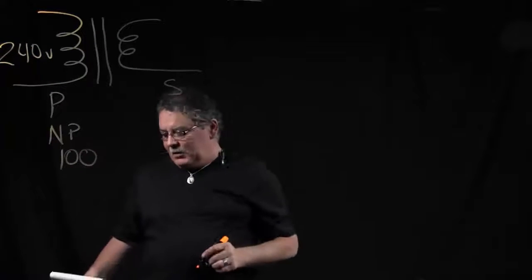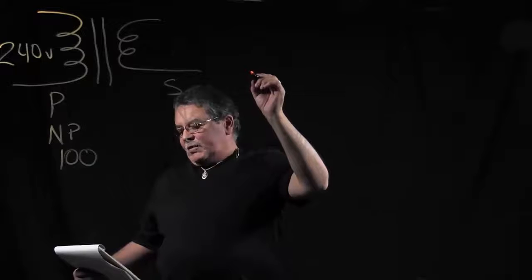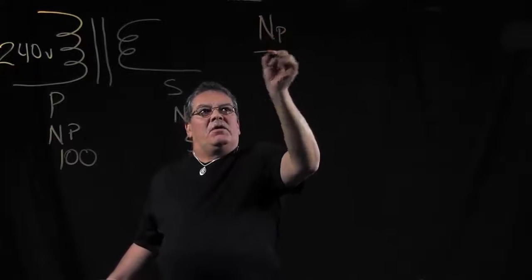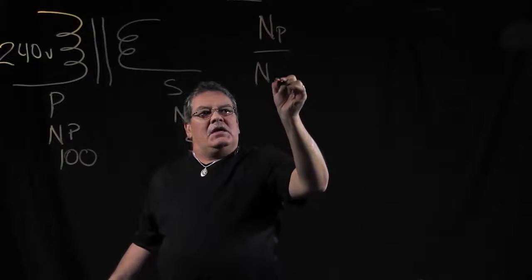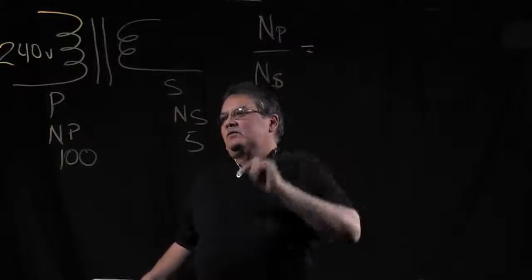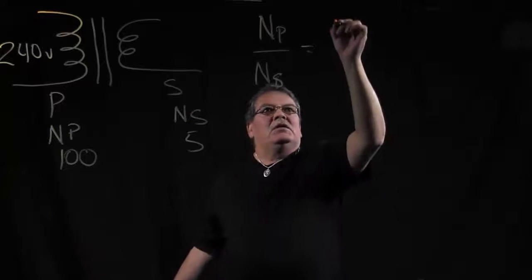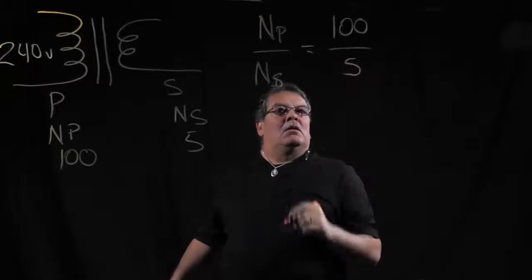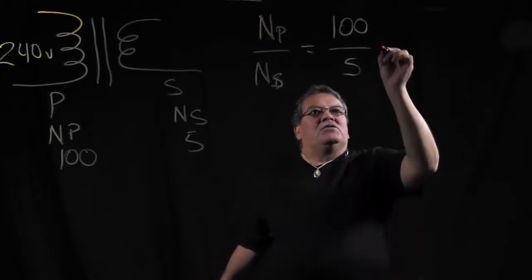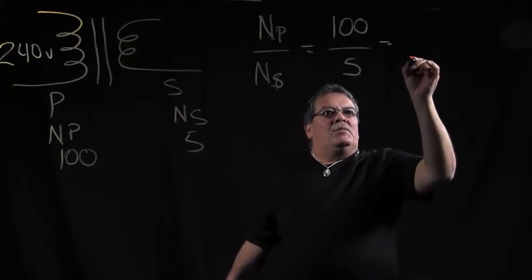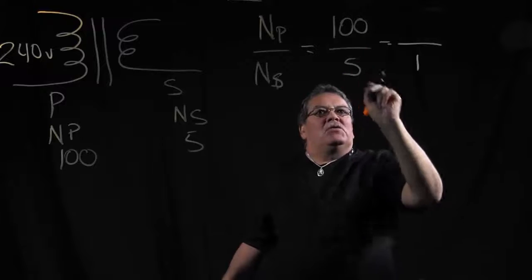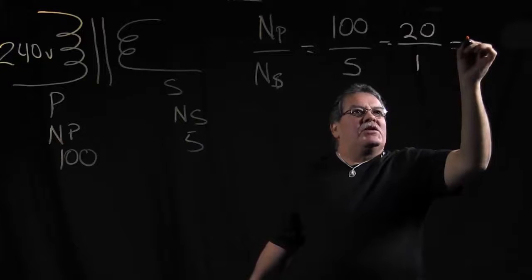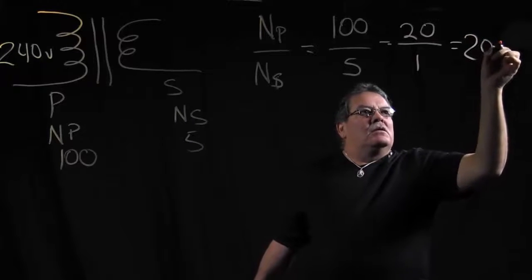OK, now here comes some of the math. So for turns ratio, basically, we already know what our primary is. So our primary is NP over NS. OK, so our turns in your primary is 100. And our turns in our secondary is 5. OK, so we could reduce this down. 5 goes into 5 one time, and 5 goes into 100 20 times. So this would equal a turns ratio of 20 to 1.